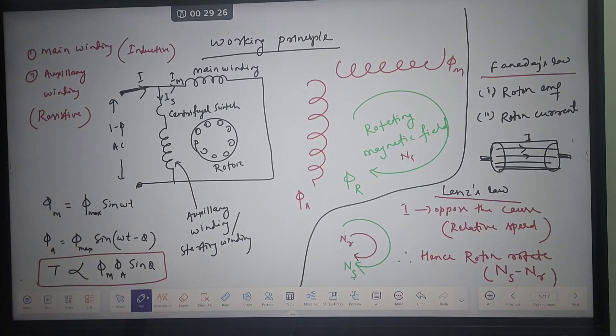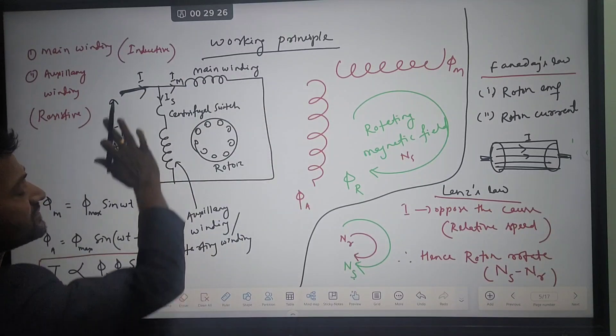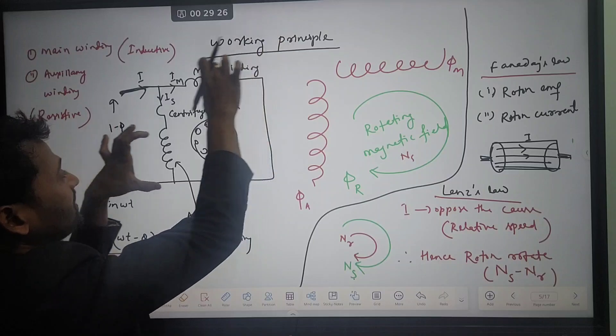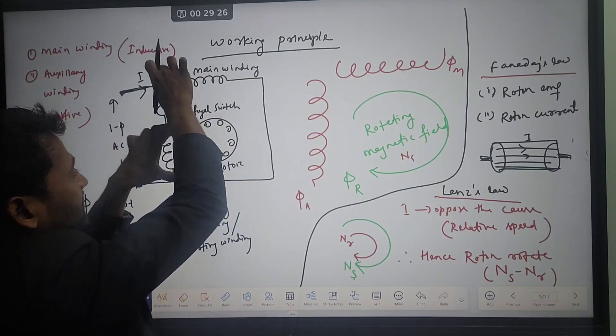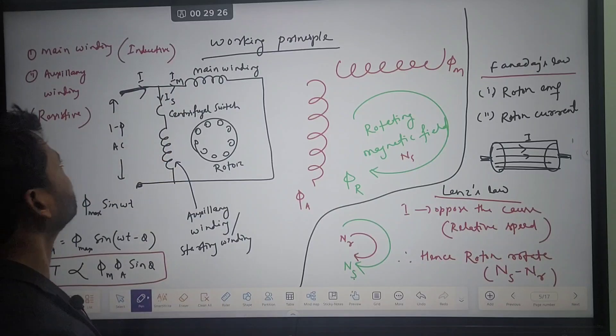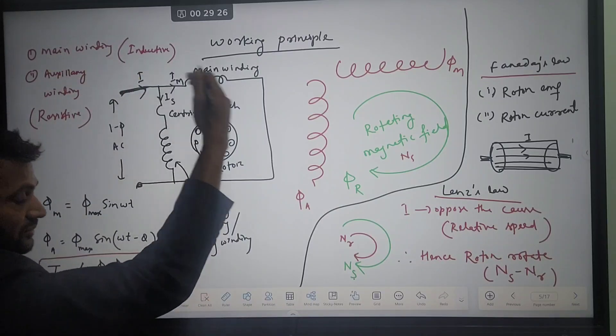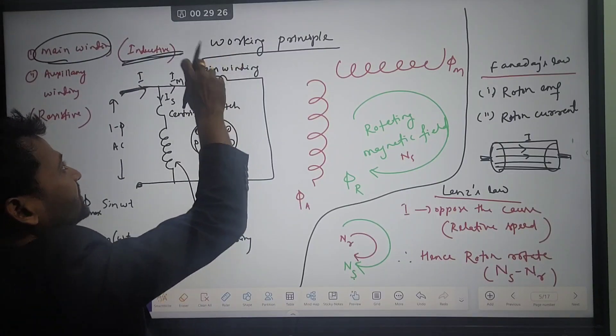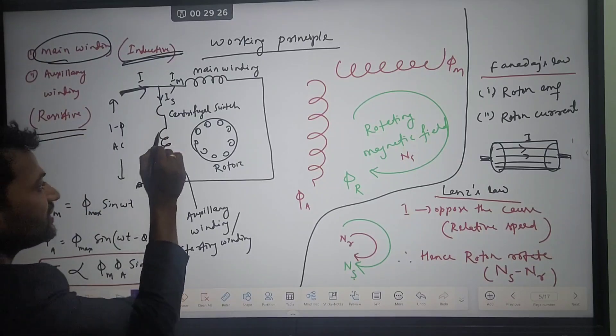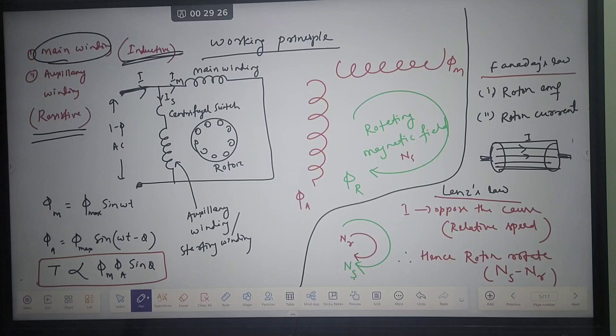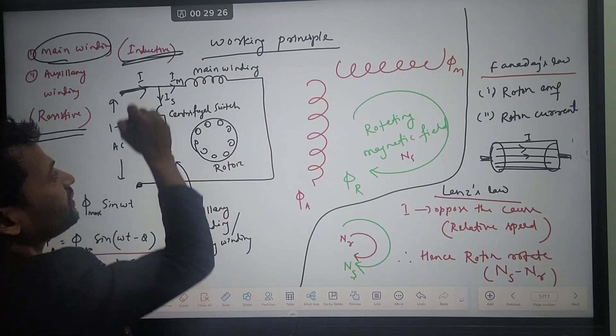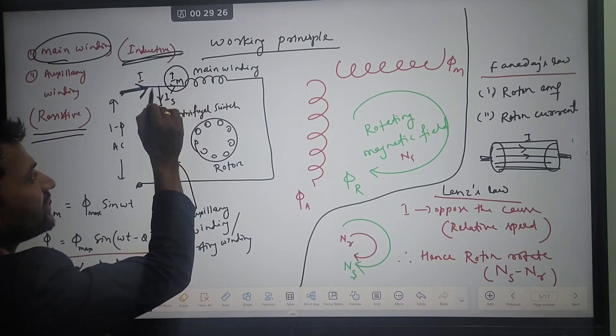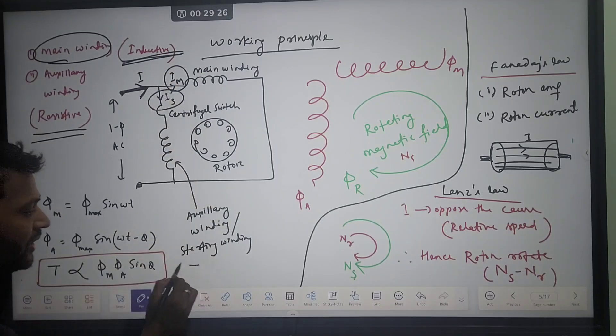Coming to the working principle: looking at the circuit diagram, the stator has two windings — main winding and auxiliary winding — connected such that the electrical angle between them is 90 degrees. The main winding has high inductance — it is a highly inductive coil — and the auxiliary winding has high resistance. Single-phase supply is given to the stator winding, and the input current divides: Im through the main winding and Is through the auxiliary winding.